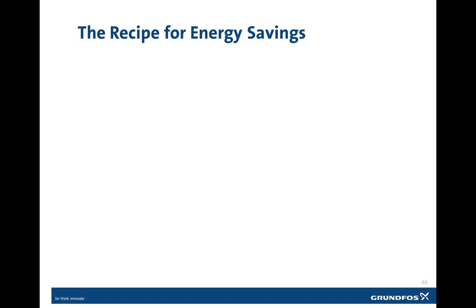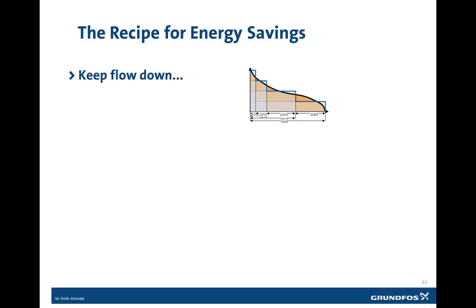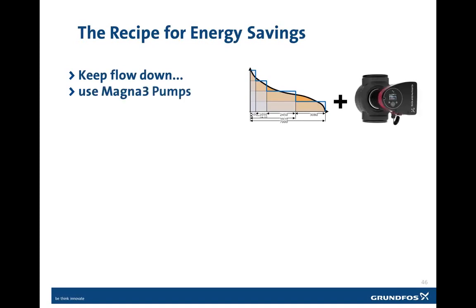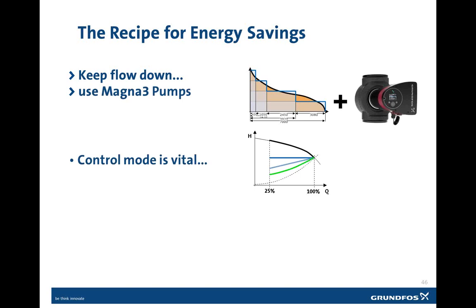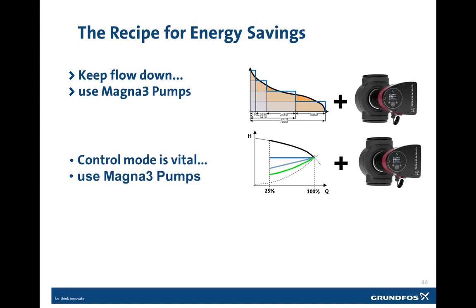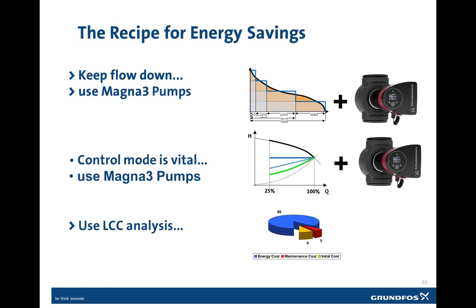So really, the recipe for energy savings is in your hand. First, the main thing we want to do in our system is keep the flow down as much as possible. And we want to be able to use Magna 3 pumps in the systems. And then control is really vital to the system. When you can use a programmable Magna 3 pump, then you can control what type of operation you want to run the system. And then also we always want to make sure that we use a life cycle cost analysis for the total cost of the system, not just a first cost analysis. And again, whenever possible, specify the Magna 3 pumps for the systems because of the additional energy savings.